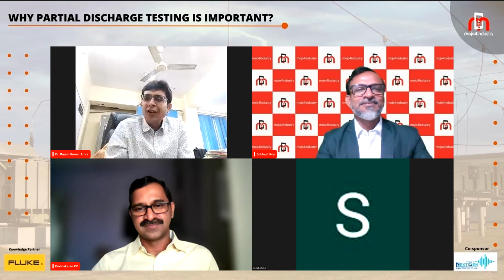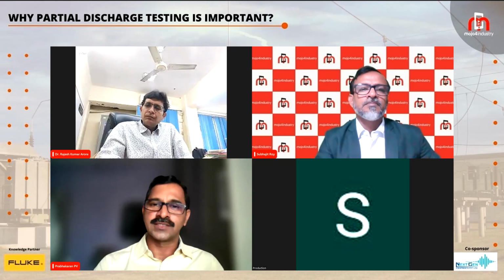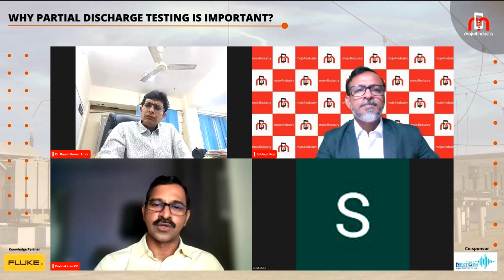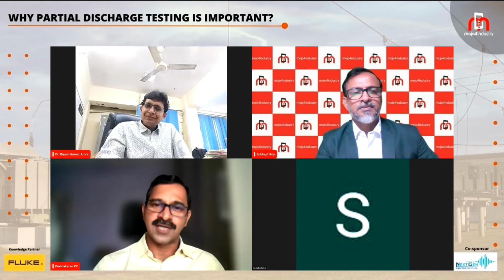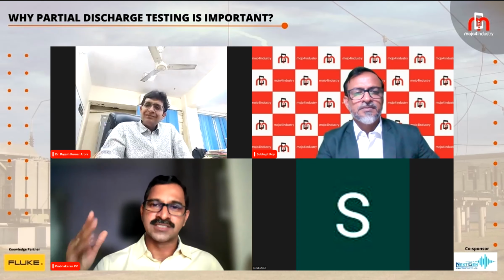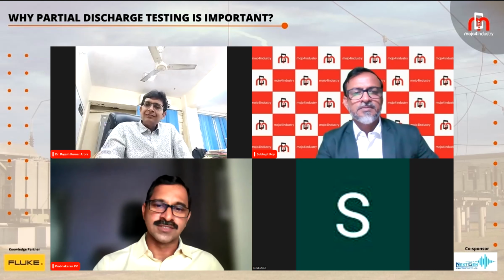If it is a cable, most of the time the cable joints can have an issue. The practice is that for any HV or MV cables, while installing itself, you have to do partial discharge detection. If you find that, then it is easy - you can just take that joint and replace it, or take the cable itself and do the replacement. But if it is an existing transformer installed for ages, and you find there is partial discharge inside, the only option you have is to take it out of service.